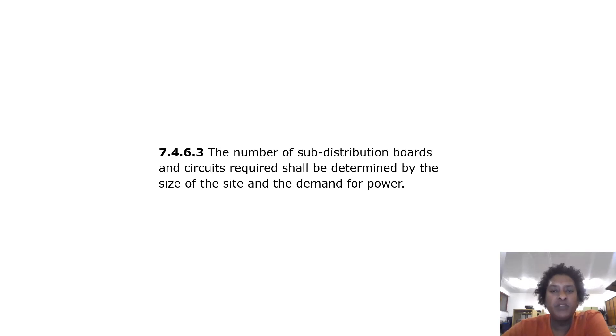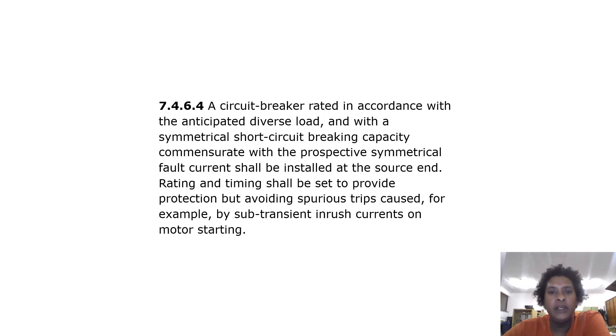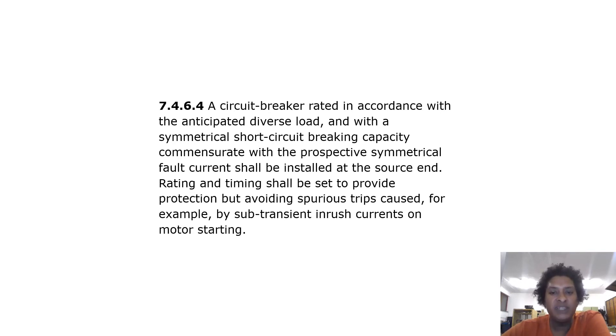The number of sub-distribution boards and circuits required shall be determined by the size of the site and the demand for power. A circuit breaker rated in accordance with the anticipated diverse load and with a symmetrical short circuit breaking capacity commensurate with a prospective symmetrical fault current shall be installed at the source end. Rating and timing shall be set to provide protection by avoiding spurious trips caused, for example, by sub-transient inrush currents on motor starting.